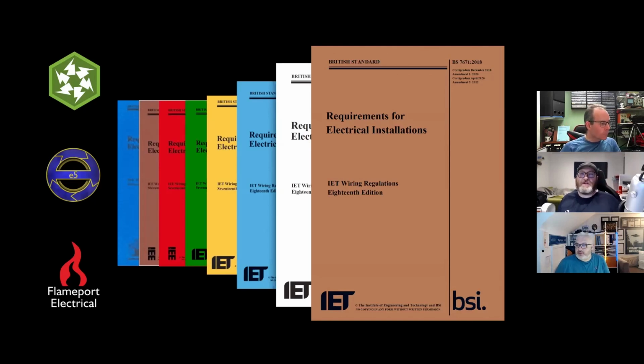All right. Richard says, so high protective conductor current is now obsolete. Older installs with or without RCDs can contain 10 milliamp or higher, so still applies. An RCD won't trip at 30 milliamps. Well, the thing is that the regulation wants us to shed down these loads to less than 9 milliamp on RCDs. Yeah, I mean, that 9 milliamp thing is in there now. Bearing in mind what we're looking at here is a draft and proposed thing, so that may or may not come in. But yeah, it won't make much sense. That's the problem of it.